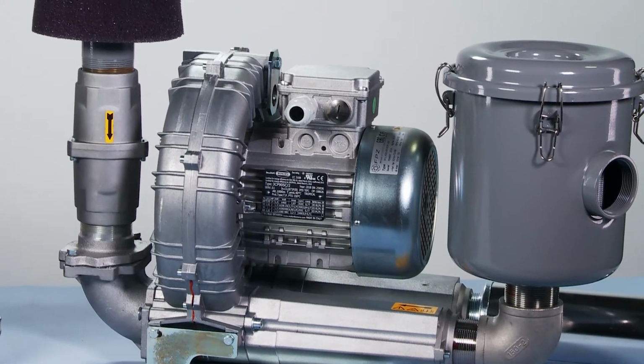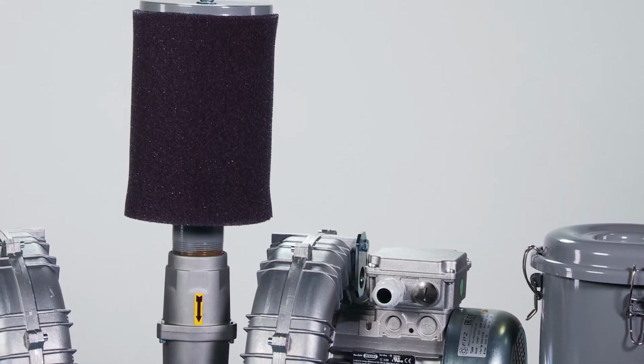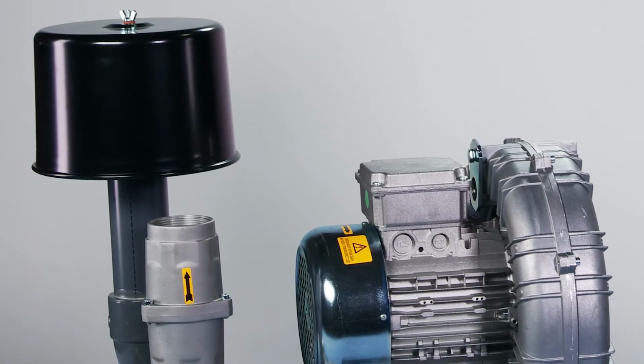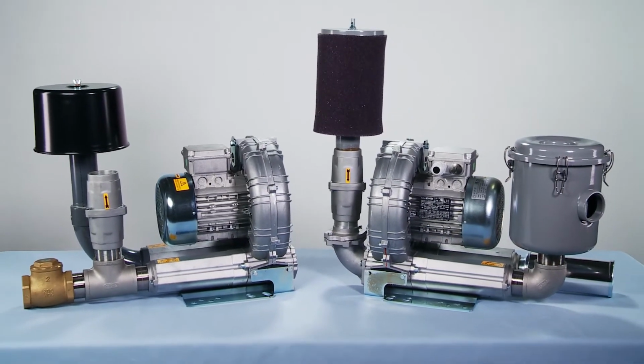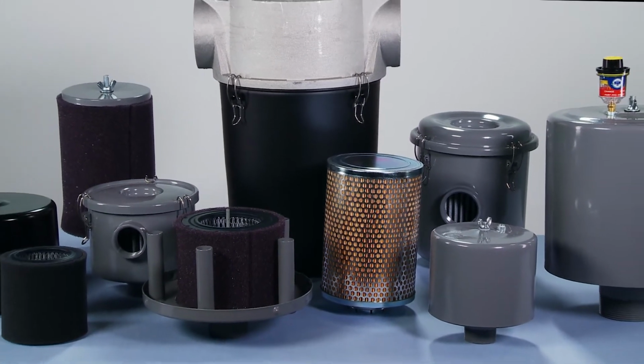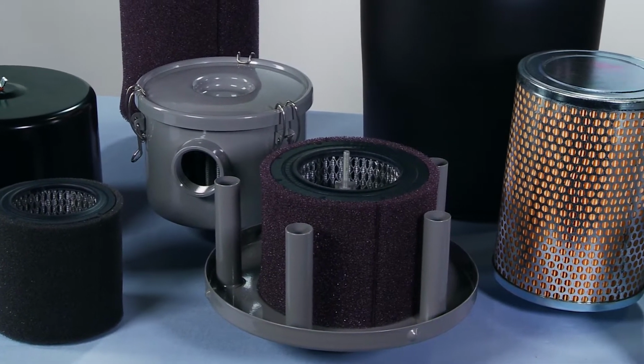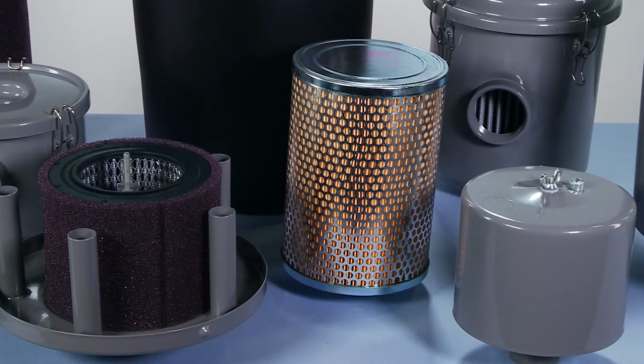The use of proper accessories is critical to assure long and trouble-free operation. There are many accessories offered by FPZ, and what is or is not used depends on the application. The most important accessories are filter, safety valve, and proper motor control. Filters are needed to prevent debris from entering the blower. If foreign material enters the blower, then it could cause damage to the impeller and other internal areas, so the use of filters is recommended on all FPZ blowers.